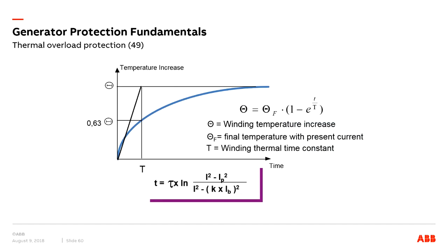Then we have the thermal overload protection. This is again very crucial from a machine protection standpoint. The heating of a machine depends on time constants, and it is an exponential curve, as we can see here, the heating characteristic of a machine, and this is due to the fact that the temperature is proportional to the square of the current. Okay, so it is not a flat characteristic, it takes a characteristic like this. Okay, and we don't want the heating to exceed the allowable or the maximum temperature withstand capability of the machine.